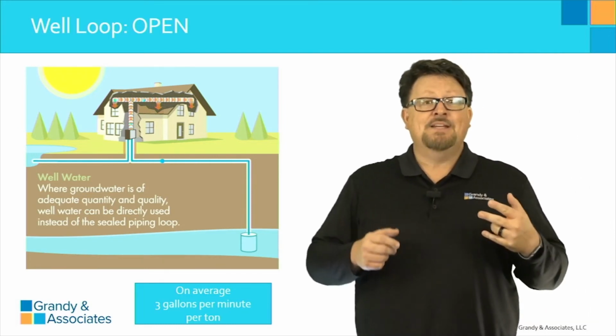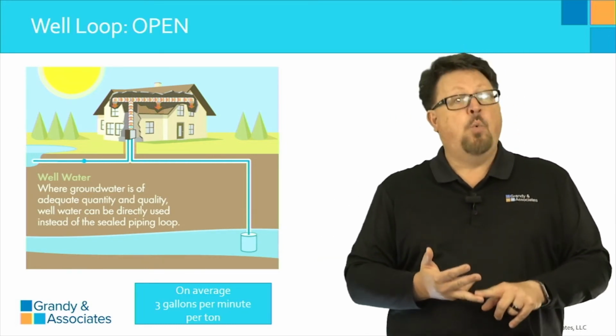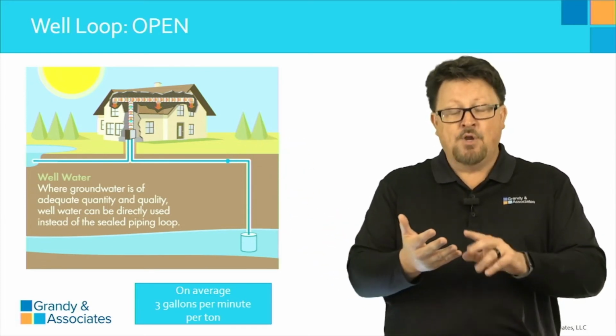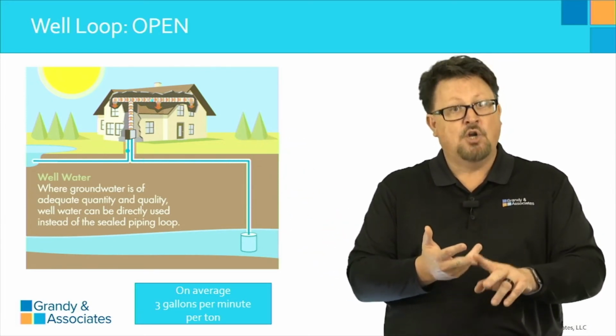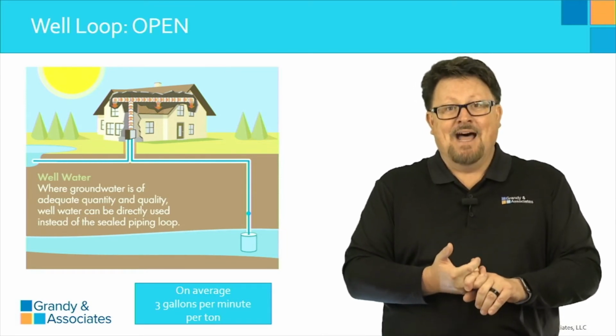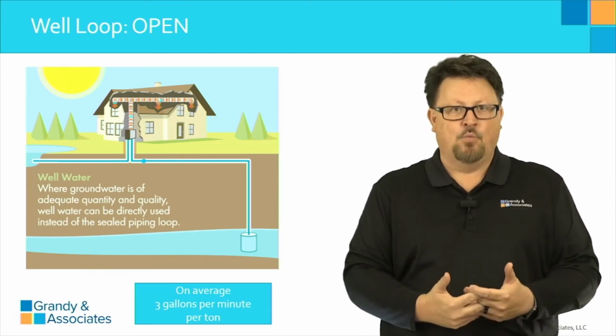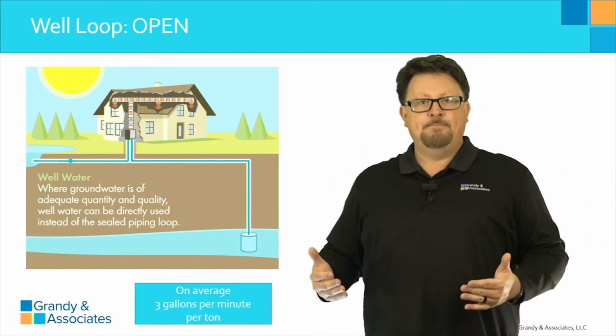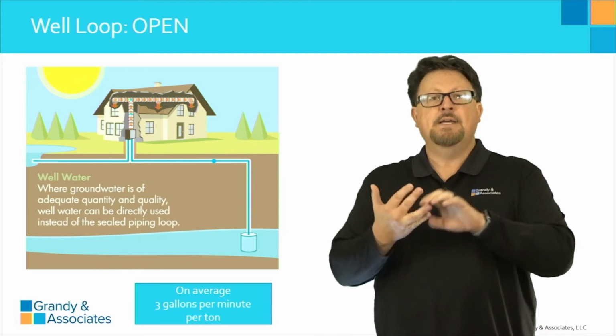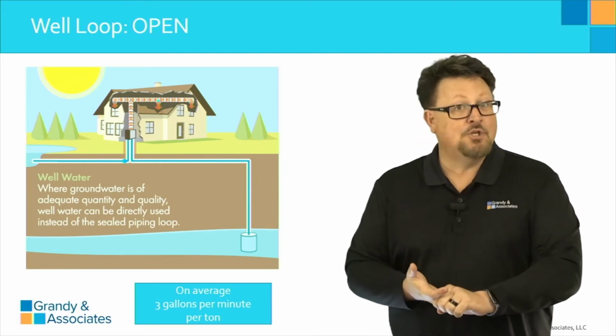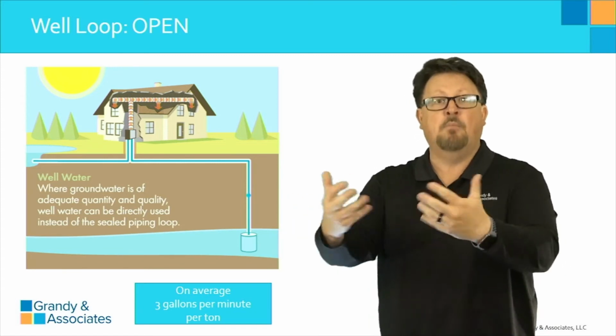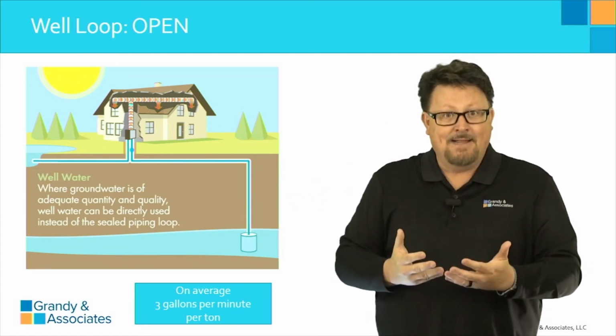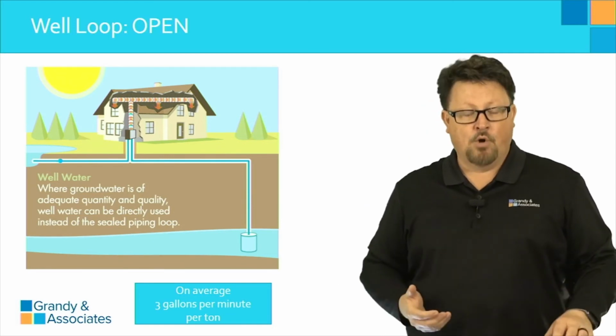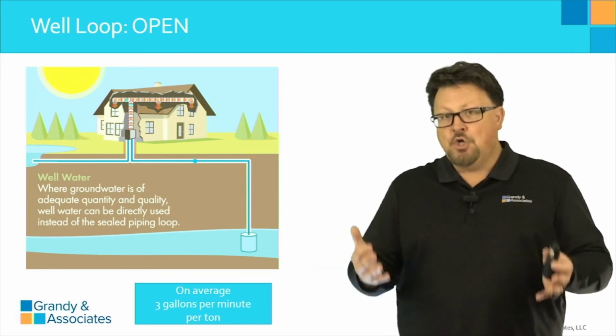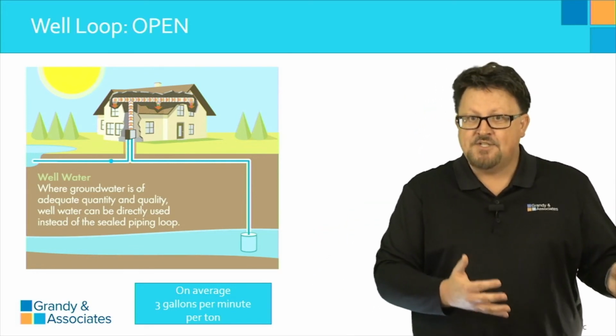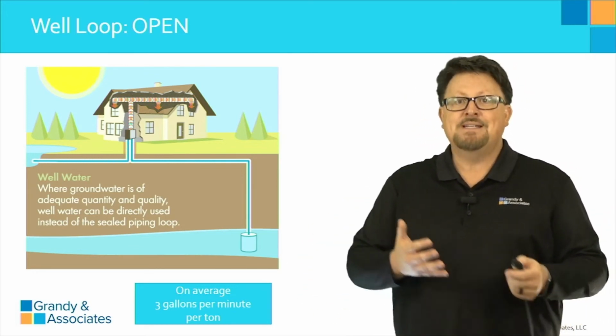Number two is not only the quantity but the quality. Since it's an open draw, I'm going to be getting a lot of silt, debris, and dirt, so I need to test both the quantity and the quality of the water. With any open loop design, you have to use specialty coils and specialty filters. Your maintenance schedule is different too, since you'll get a lot more debris in this design, so you have to clean the system more frequently. So all of these designs are good, but they each come with little differences and nuances you have to be aware of for proper design and function.